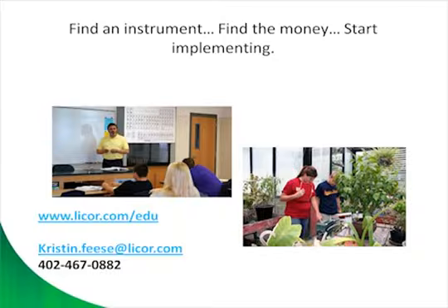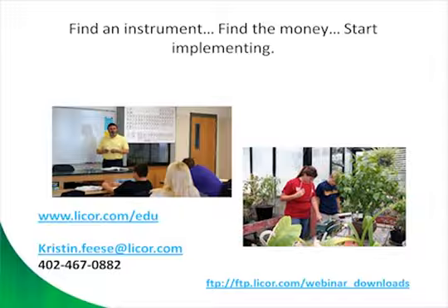I think some things to keep in mind is make sure that the instrument you have is rugged, it's reliable, highly accurate, that it's not going to be easily disturbed. The second thing is to save your configuration and save all of your data on a separate, like on your computer or something like that, so that you can download that back onto your instrument right before you go out and use it.